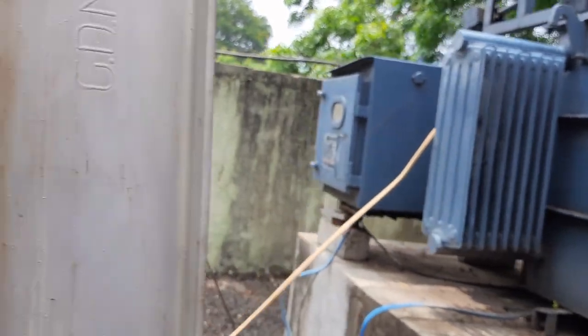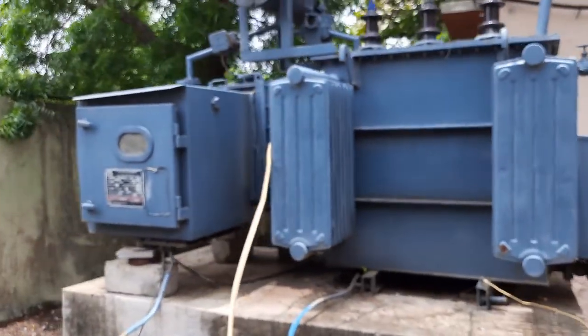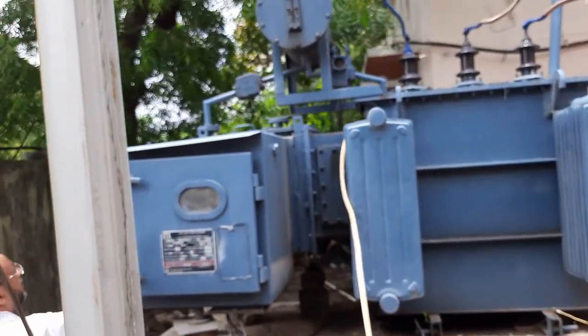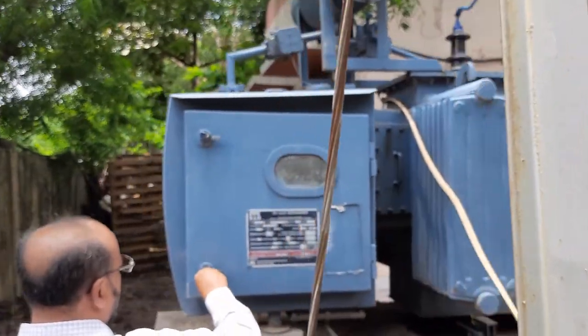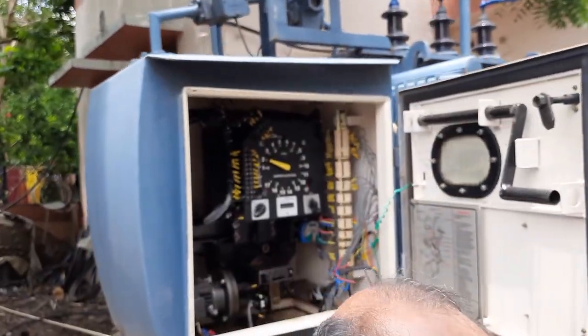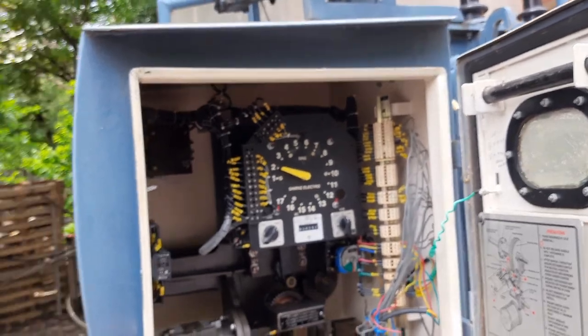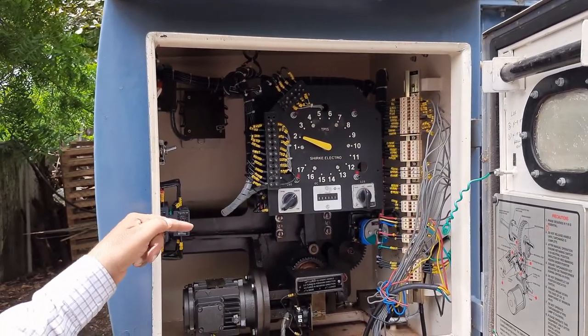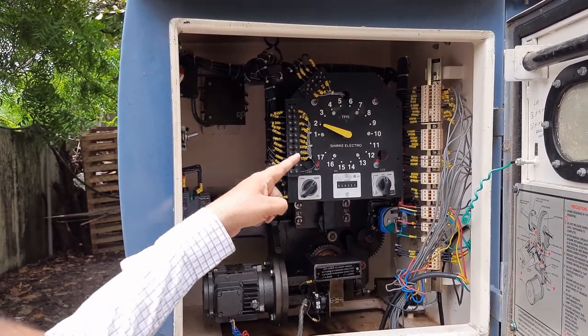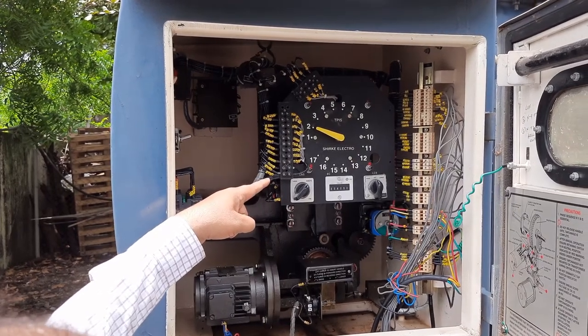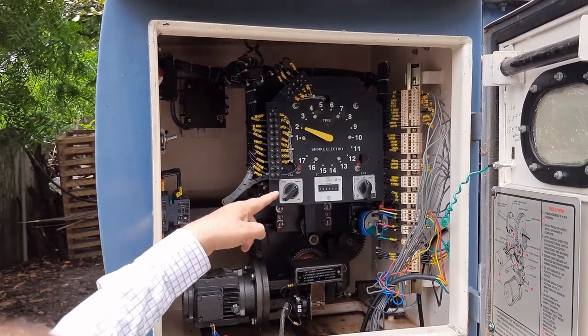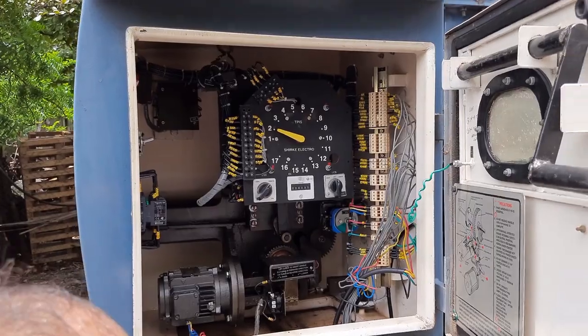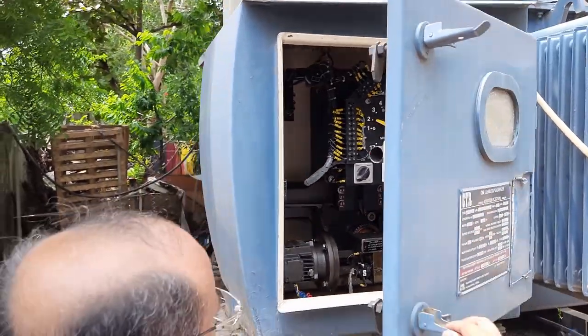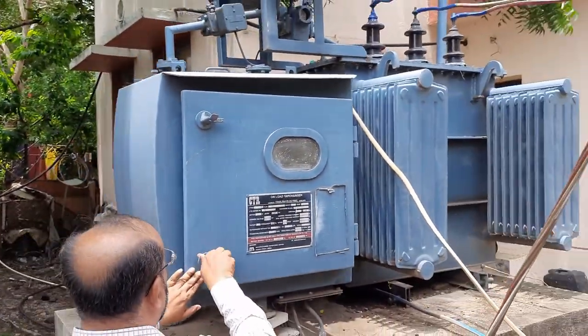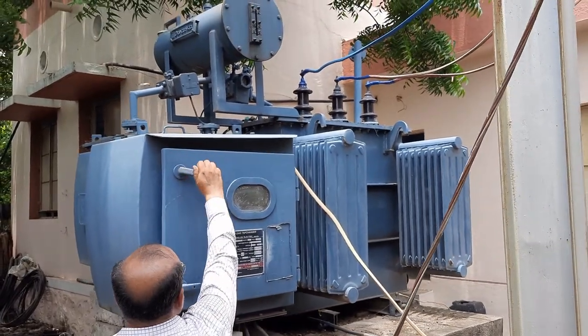This is the on-load tap changing arrangement. When the voltage changes, with the help of these gear systems and automatic controlling, the tap number is going to change. Presently it is on tap number 2, but as the voltage decreases, the tap number also increases. So this is the facility to maintain a constant terminal voltage in the college premises.